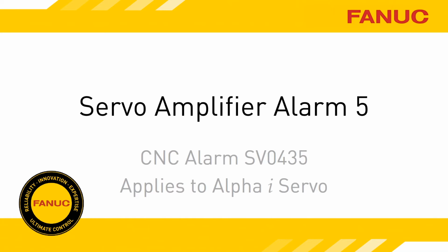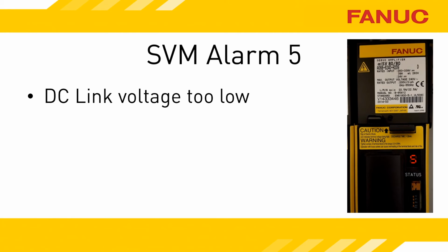Alarm 5 is displayed when the DC link voltage is too low. This presentation will demonstrate the troubleshooting procedures involved. An alarm 5 on a servo amplifier indicates that the DC link voltage is below minimum. The DC link provides the voltage used by the motors to turn. Nominal voltage of the DC link is 300 volts for standard alpha I amplifiers and 600 volts for high voltage units.